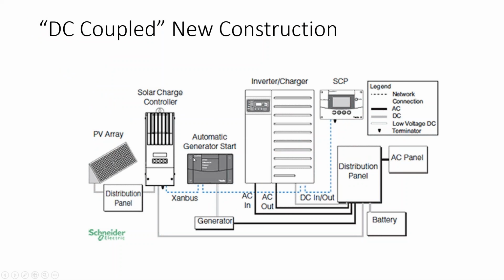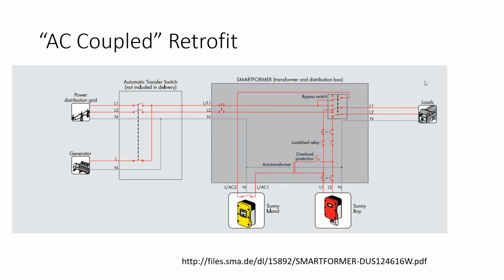Is it the only solution for off-grid? No. Most off-grid arrays are going to have a generator, so if your battery inverter runs out of batteries, you could crank the generator, charge the batteries back up, and provide the grid signal for the solar array to turn on. You could crank the generator for just half an hour if the sun's up, to give the batteries enough juice to maintain the grid while the solar array supplies the load and charges the batteries back up.